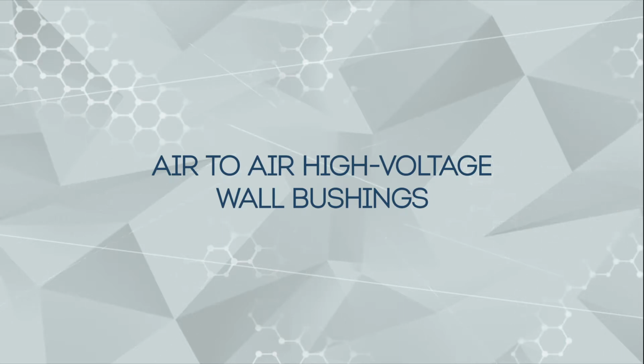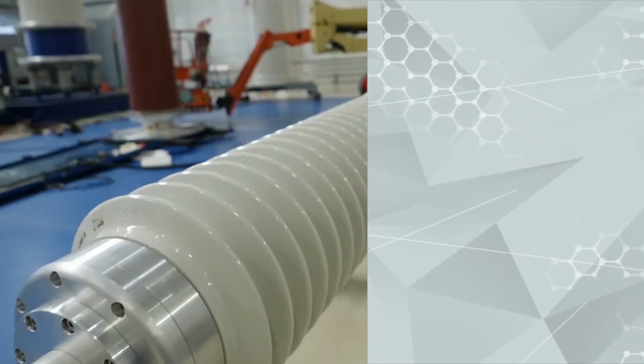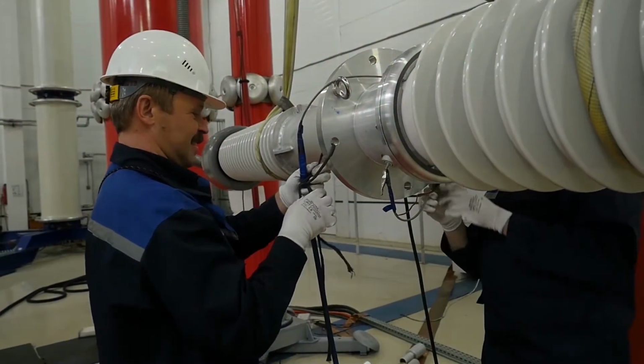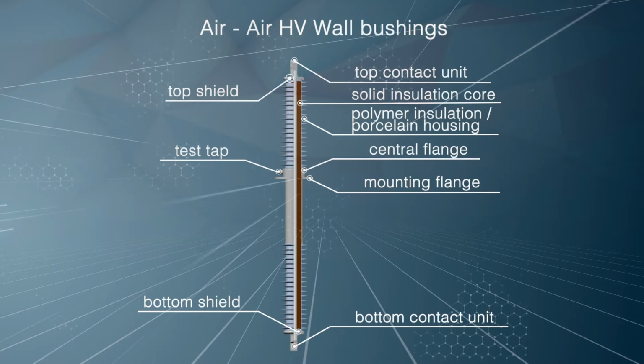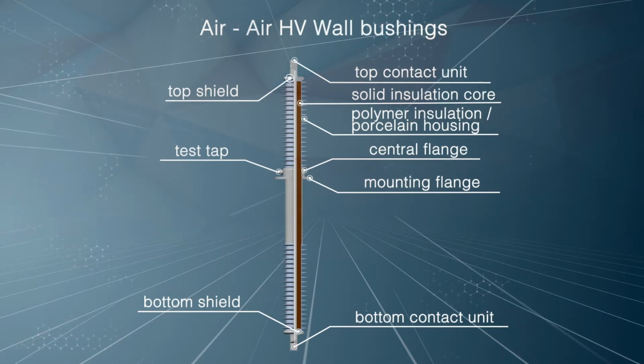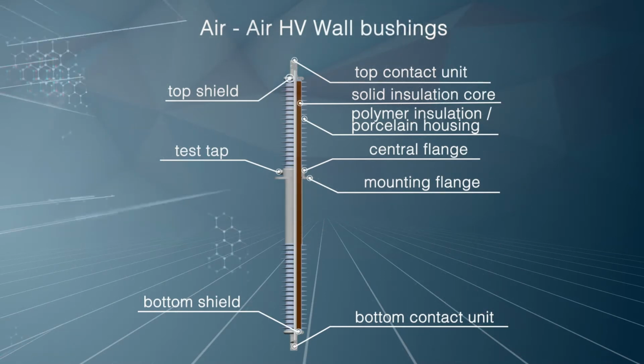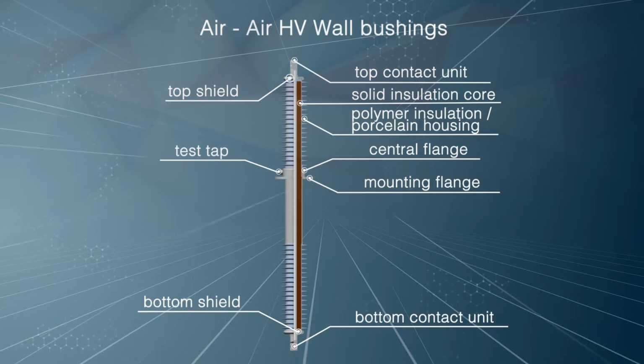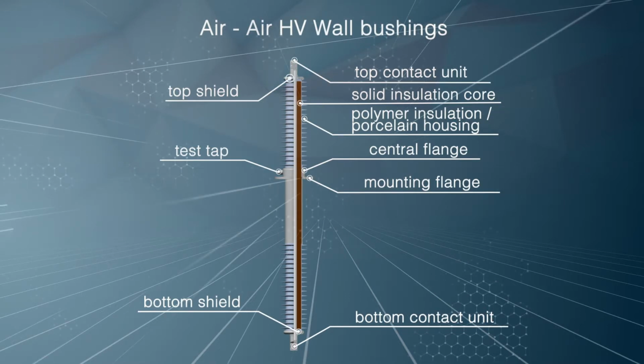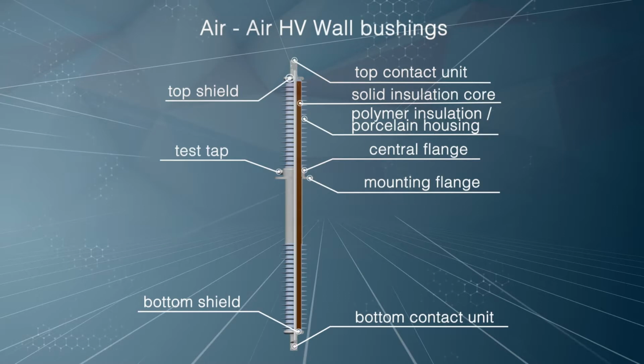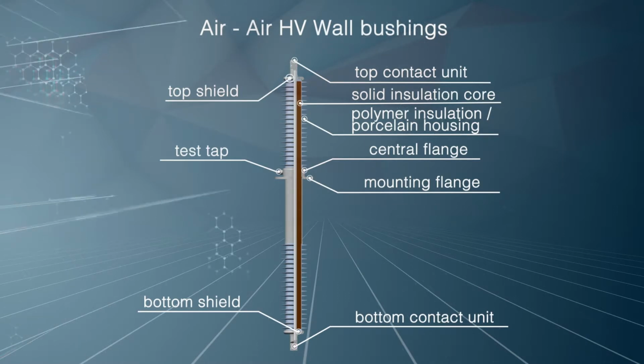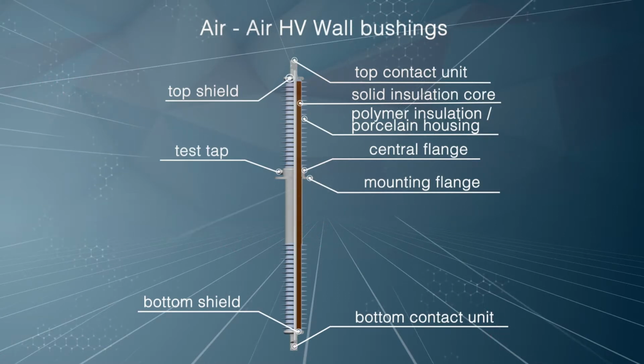Air-to-air high-voltage wall bushings. The bushings are intended for installation in walls and floor slabs of switch houses. Izolyator makes wall bushings only with condenser-type solid insulation core, with RIP technology as the most effective. Air-to-air bushings can have a porcelain external insulation or polymer finning. The flange is used for fastening the bushings on its installation place and can be either round or square.